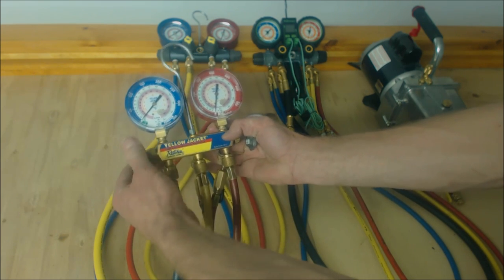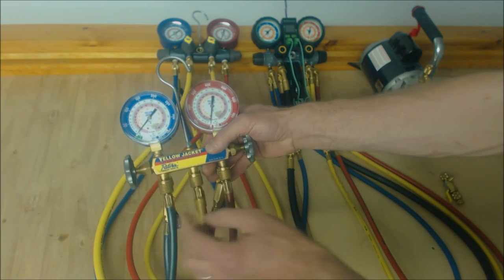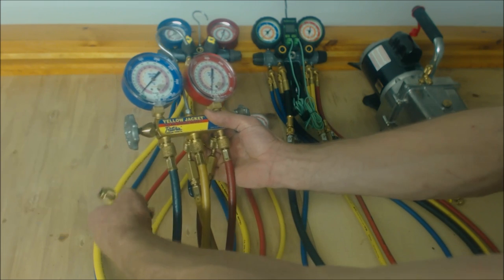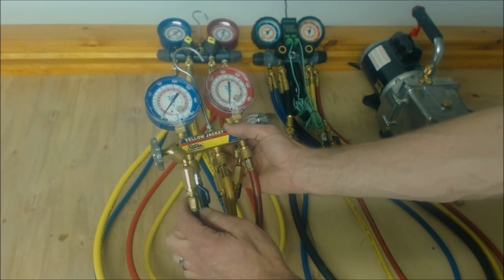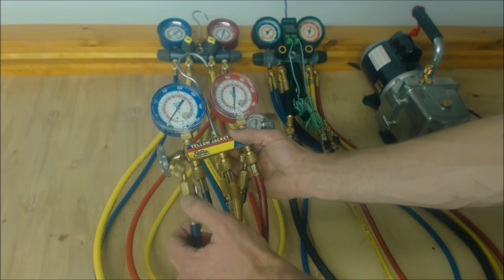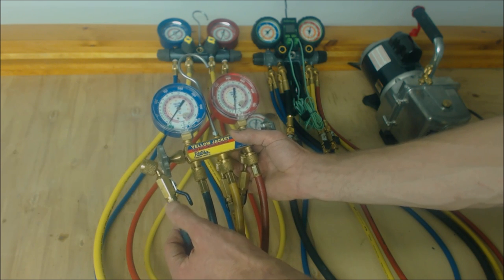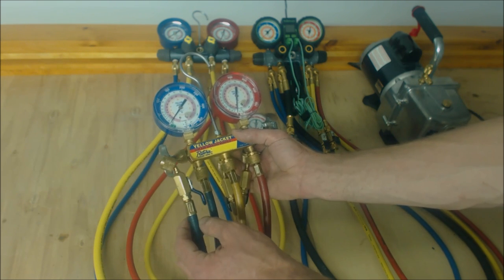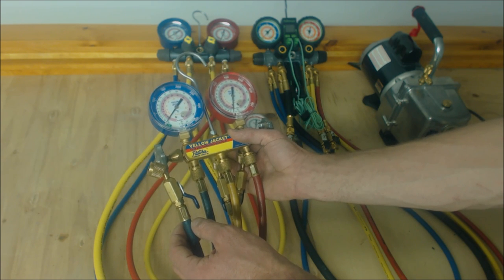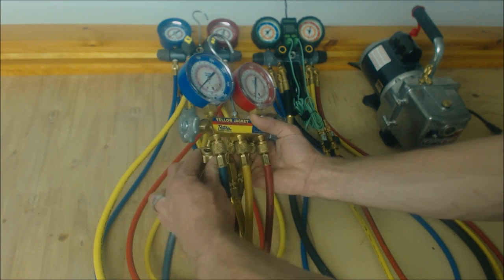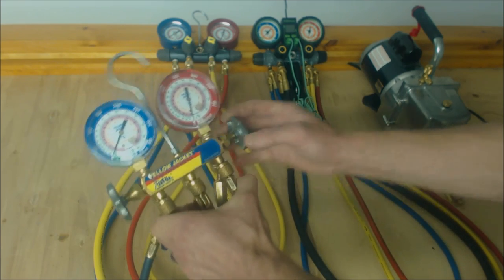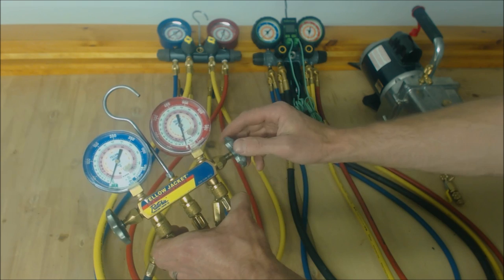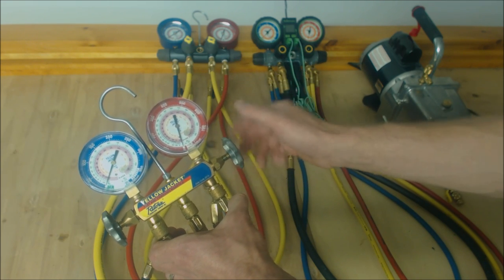I do like the hoses that have the manual off, as you've seen in a lot of the videos. This is a manual low loss valve on the hose. I like it to be at the very end and I like to have no temporary connections with rubber grommets that could leak potentially. I like these and also the quick disconnect low loss fittings, but I do prefer these. I can open these valves pretty quickly. There's no need to crank on these afterwards. You just open them up and they're good to get a full flow for a vacuum.